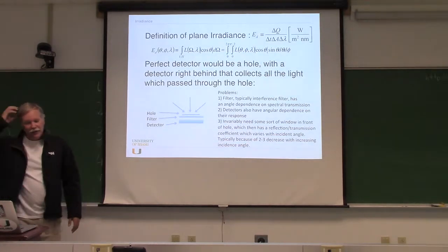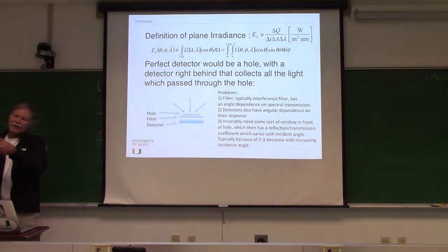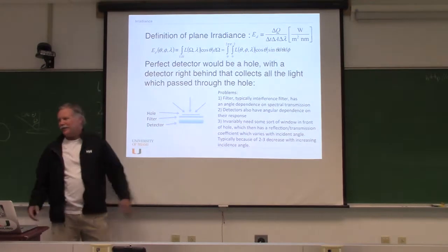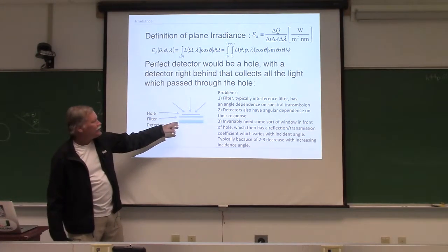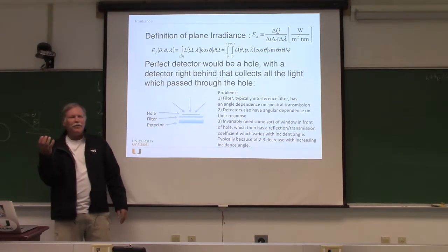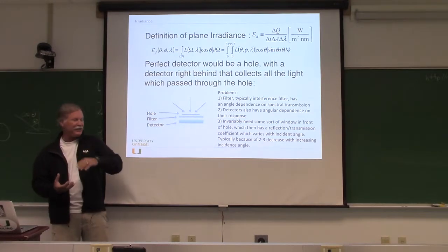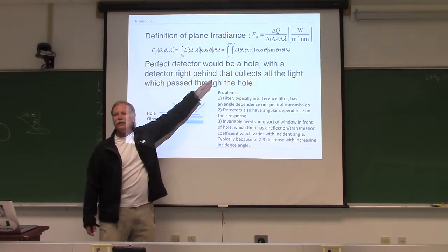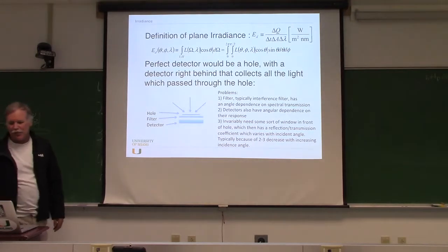For planar irradiance, the ideal sensor is just a hole that collects whatever comes through it, but in practice detectors have angular response issues. If you want to measure spectral planar irradiance, a filter is needed whose response varies with the angle of incident light. The detector also has an angular response, and you need a window to keep water out, which reflects more light at higher angles. So a simple detector without any special design is a pretty poor irradiance sensor.